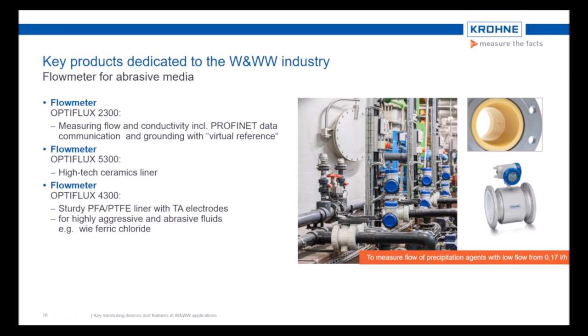Another key product are our special lined OptiFlux 4300 with a sturdy Teflon liner and our OptiFlux 5300 with an indestructible ceramic liner. Both flow meters are dedicated to be used for the flow measurement of highly abrasive or aggressive media. In water and wastewater applications, it is mostly used for dosage of chemicals like ferric 3 chloride, which is used for the elimination of phosphate. So both flow meters are suited to very, very small diameters and very low flows starting from 0.17 liters per hour with a diameter of 2.5 millimeters. So ideal when you have a drop per drop dosage.